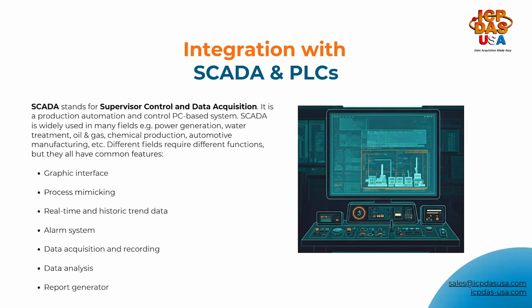Now, while each industry may have its own unique needs, SCADA systems typically share a set of essential features: a graphic interface that provides operators with an intuitive visual overview of processes, process mimicking that reflects real-time changes in system status, access to both real and historical trend data for deeper insight, a built-in alarm system for immediate fault detection, reliable data acquisition and recording, tools for data analysis and troubleshooting, and finally, automated report generation for documentation and compliance.